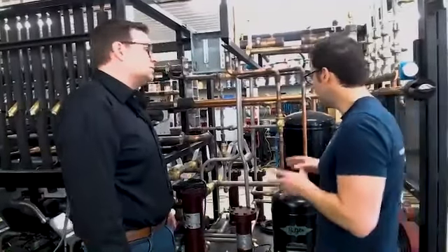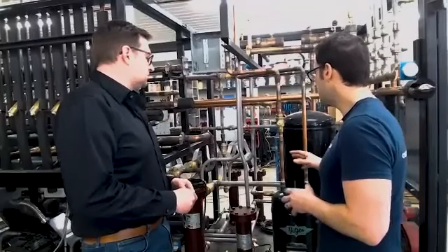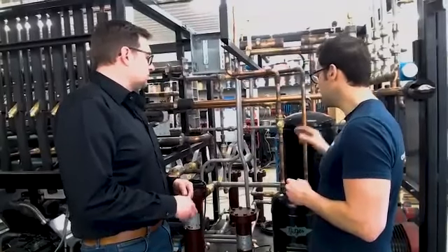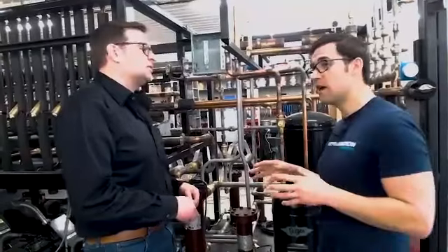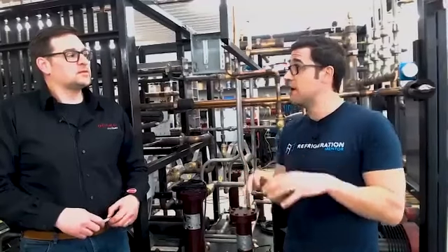I just like how clean it's done — the welds are amazing, that's an art in itself. This is something you'll start to see more of depending on where you're at in the world. In Europe there's a lot of K65 and high pressure copper, even in the US too, but here in Canada it's different — the field piping on the high side needs to be stainless steel.